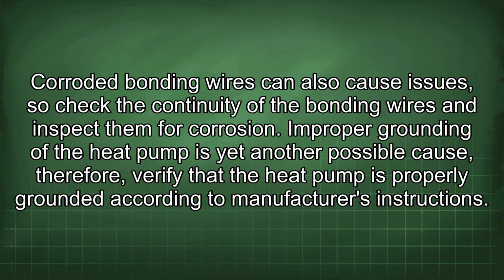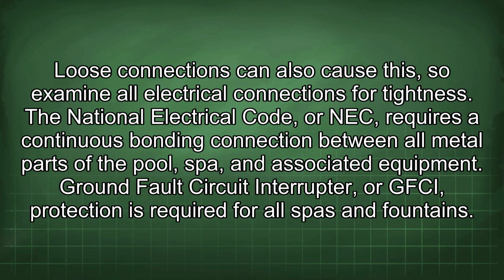Improper grounding of the heat pump is yet another possible cause. Therefore, verify that the heat pump is properly grounded according to manufacturer's instructions. Loose connections can also cause this, so examine all electrical connections for tightness. The National Electrical Code, or NEC, requires a continuous bonding connection between all metal parts of the pool, spa, and associated equipment. Ground fault circuit interrupter, or GFCI, protection is required for all spas and fountains.